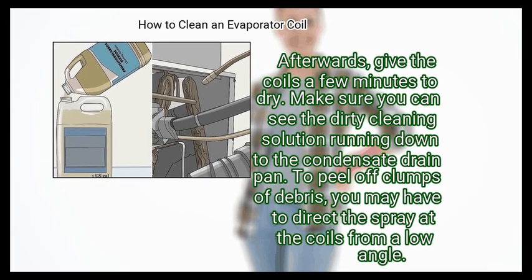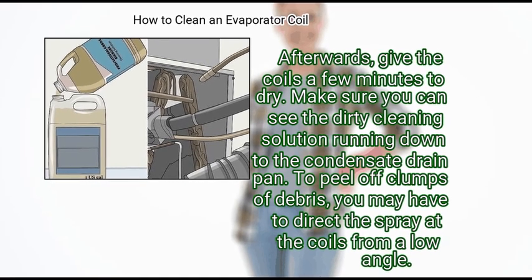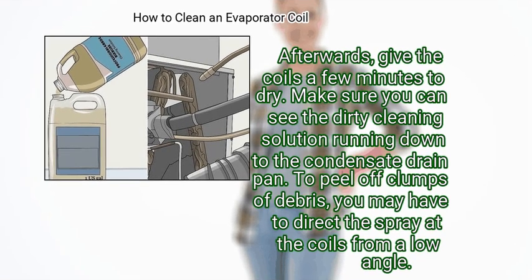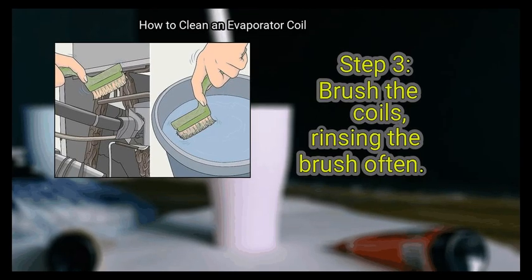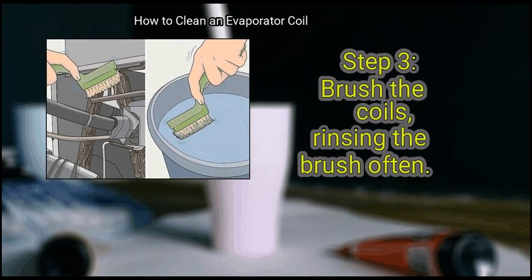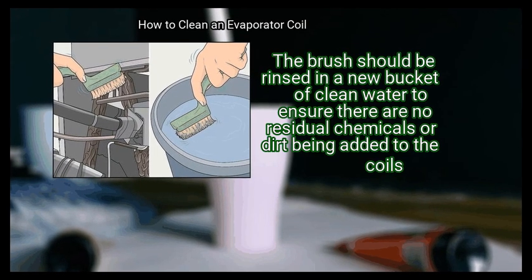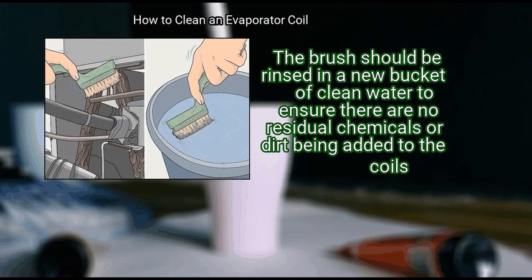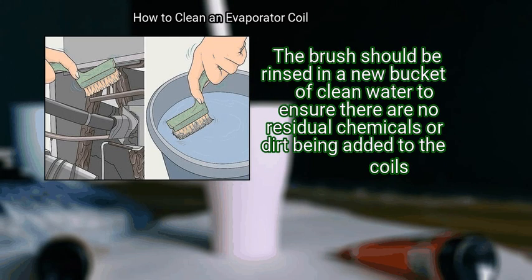Afterwards, give the coils a few minutes to dry. Make sure you can see the dirty cleaning solution running down to the condensate drain pan. To peel off clumps of debris, you may have to direct the spray at the coils from a low angle. Step 3. Brush the coils, rinsing the brush often. The brush should be rinsed in a new bucket of clean water to ensure there are no residual chemicals or dirt being added to the coils.